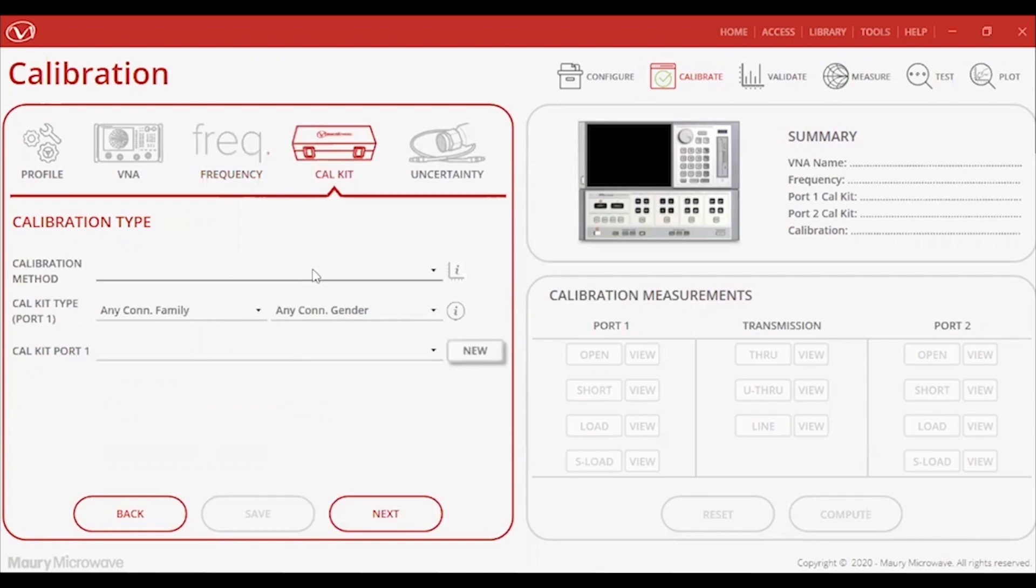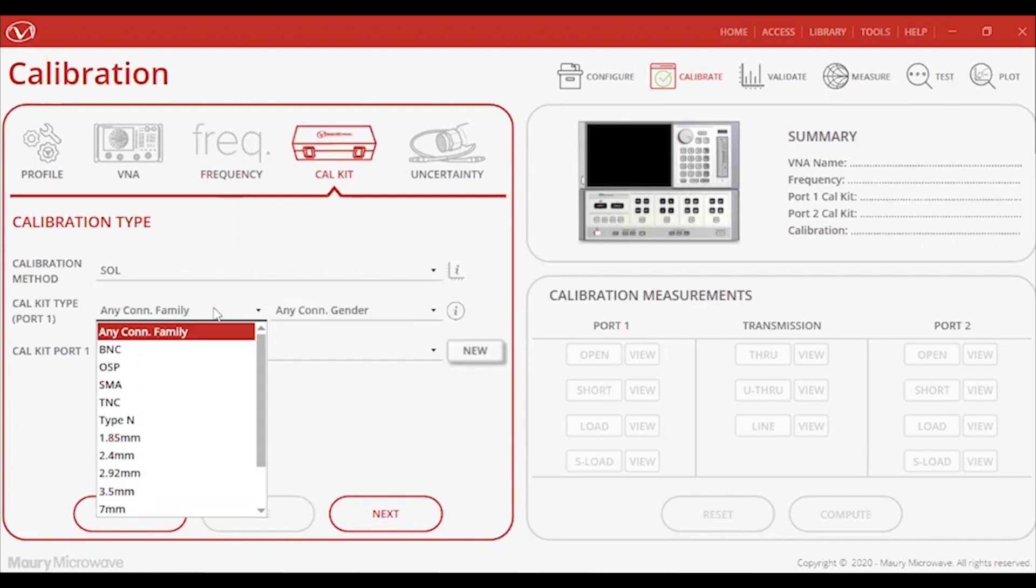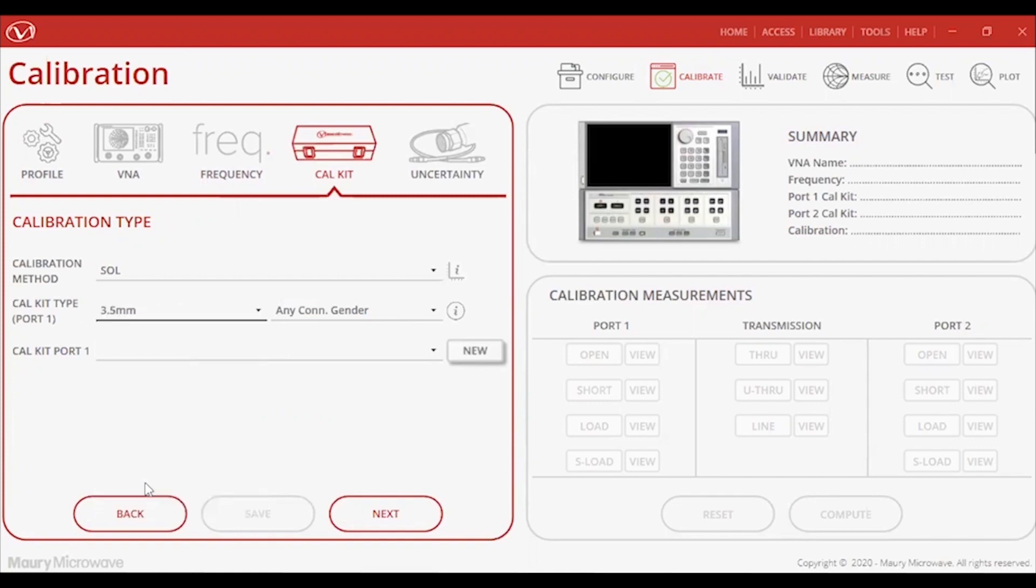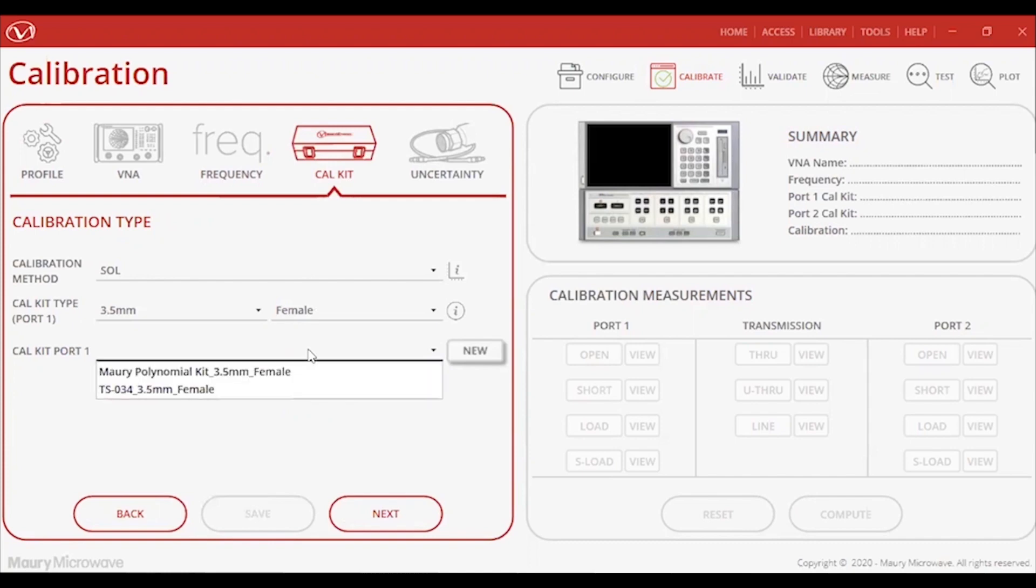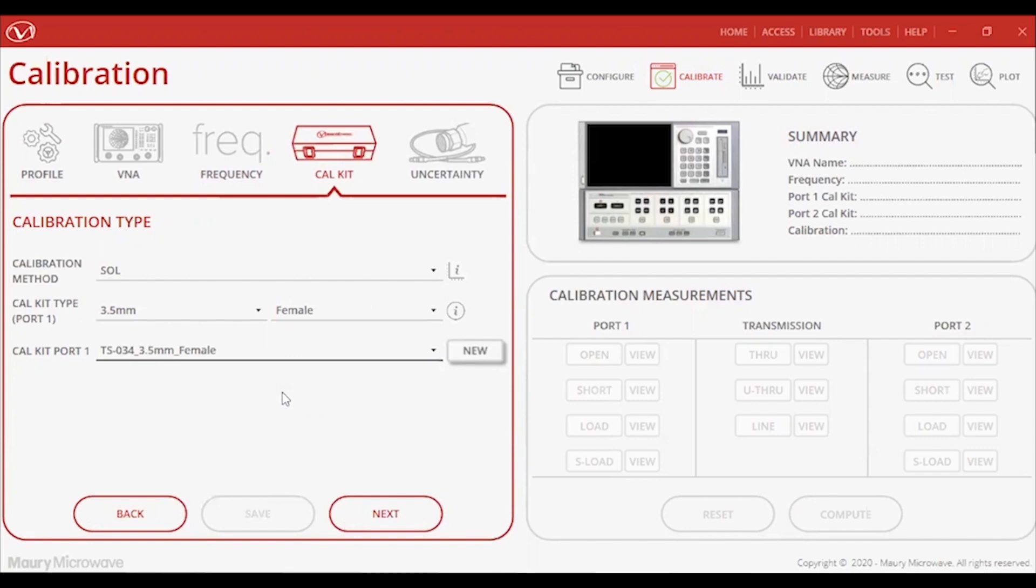Once the frequency range is fully set up, I can then select the CalKit and method of calibration. For the CalKit, either choosing between a polynomial CalKit or a characterized CalKit with uncertainty. As for the calibration methods, the list is also quite extensive and ranges from SOLT, TRL, LRM, and you can even perform on-wafer calibrations. In my case, I chose to go with the one-port SOL calibration method using the characterized CalKit, which will also empower measuring S-parameters with uncertainty.